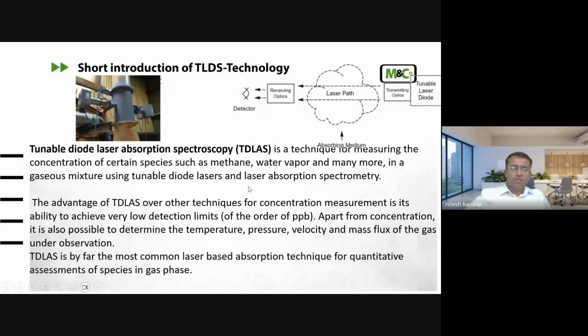This technology measures the concentration of certain species such as methane, water vapors, and many other components. The advantage of TDLS over other concentration measurement technologies is its ability to achieve very low detection limits. And apart from the concentration, it is also possible to determine the temperature, pressure, velocity, and mass flux of the gas under observation.